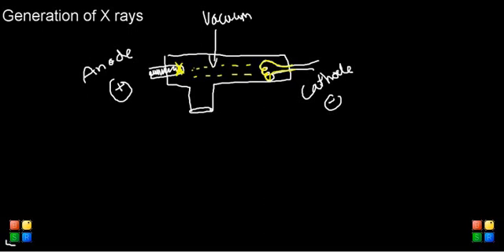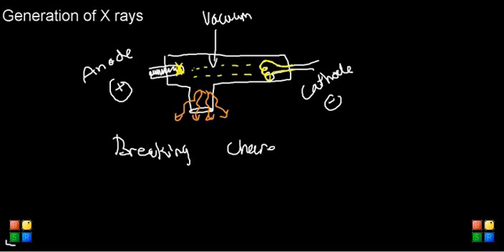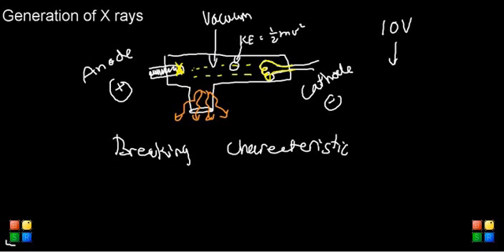When electrons interact with the anode material, we get x-ray photons through two main mechanisms: braking radiation and characteristic radiation. It's also important to understand that these electrons are moving and have kinetic energy. The greater the voltage difference between the anode and cathode, the faster the electrons move. For example, 10 volts gives 10 electron volts of kinetic energy per electron, and 20 volts gives 20 electron volts.